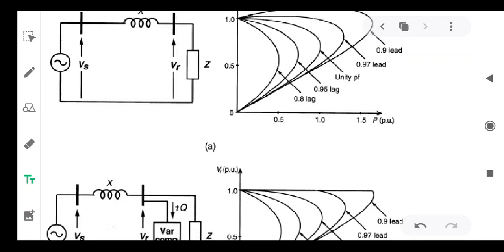The power factor of the system can be improved by using a fixed compensator like a shunt capacitor. By using that shunt capacitor, the PV curves have been improved, but the voltages may not be kept constant at 1 pu for all kinds of compensators. Therefore, by increasing the size of the compensator, we can improve the voltage stability, but the voltages may not be at a constant value.